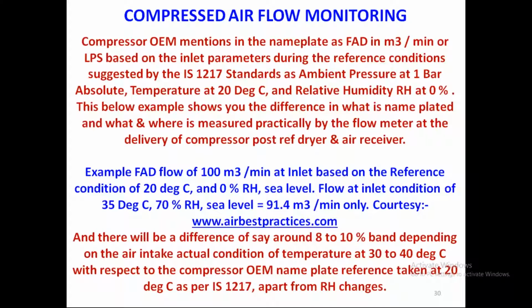Normally when you visit the industry, you will find the outer surrounding ambient air temperature around 40 degrees, and inside the compressor house it will be 45 or 47. It is a bad practice. We have to tell the industry to improve upon housekeeping to reduce the temperature inside the compressor house. So straight away there is an 8 to 10% difference in flow between what is measured as the actual flow and what is stated on the nameplate. We have to accept that and measure it, and accordingly do the calculation as an energy auditor.